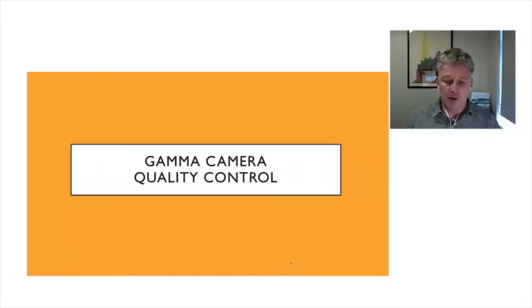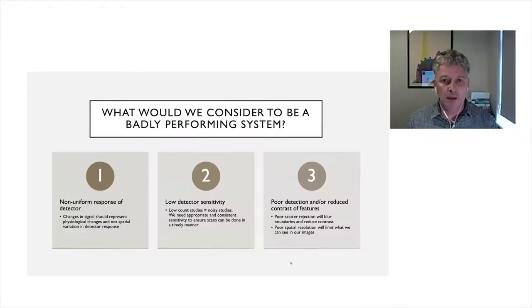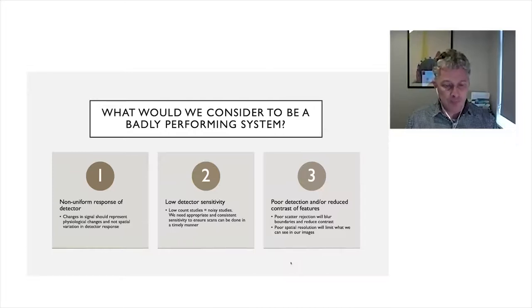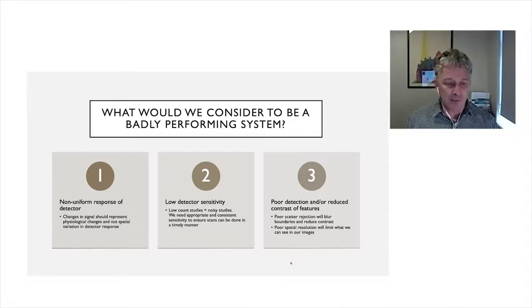Now let's get to the actual gamma camera quality control. What we're trying to do is ensure good imaging performance. To do that, it's important to consider what a badly performing system would look like. A bad system would first have a non-uniform response across the detector — changes in signal should represent physiological changes, not spatial variation in detector response. So it's important to assess the uniformity of response. Second, we need to look at detector sensitivity: fewer counts per voxel means noisier studies, so we need appropriate and consistent sensitivity.